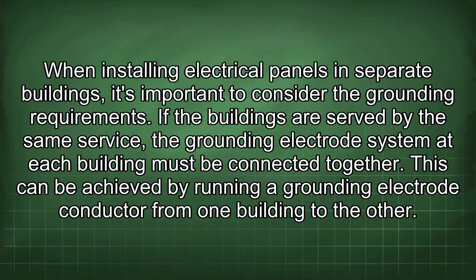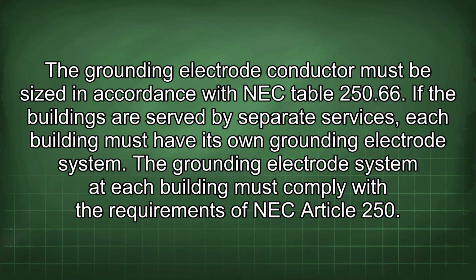When installing electrical panels in separate buildings, it's important to consider the grounding requirements. If the buildings are served by the same service, the grounding electrode system at each building must be connected together. This can be achieved by running a grounding electrode conductor from one building to the other. The grounding electrode conductor must be sized in accordance with NEC Table 250.66. If the buildings are served by separate services, each building must have its own grounding electrode system.